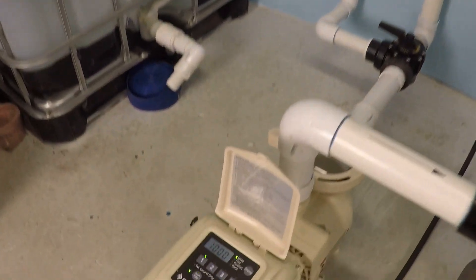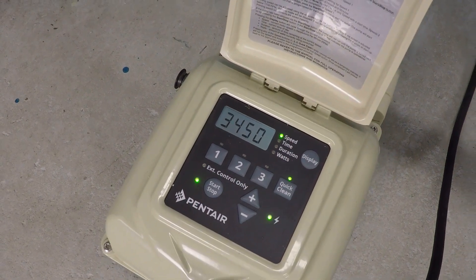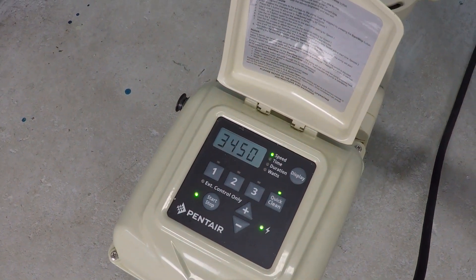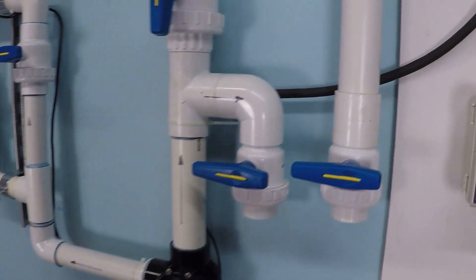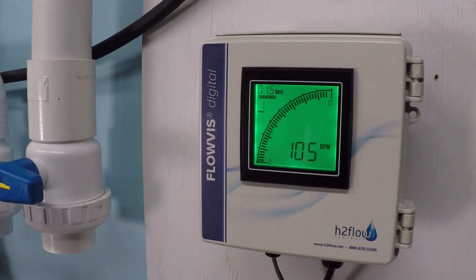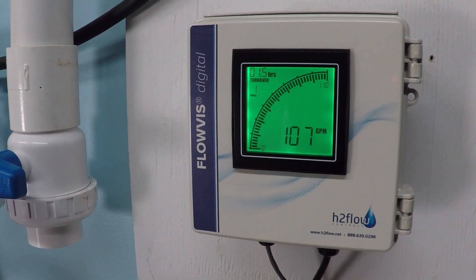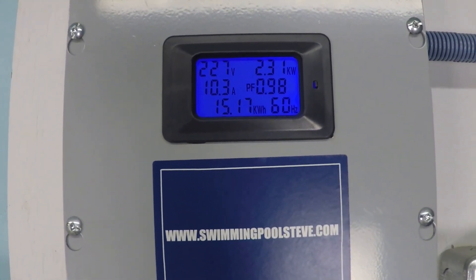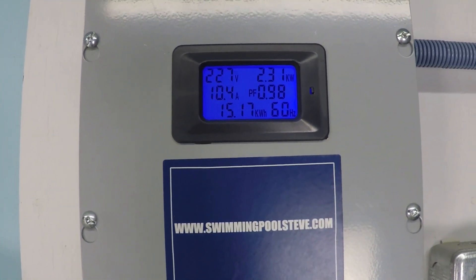Let's go ahead and try high speed operation at 3,450 rpm and take a look at the flow rates and electrical consumption. The flow meter is reading 107 to 108 gallons per minute, and the power reading in the top right corner shows 2.32 kilowatts — that's 2,320 watts.